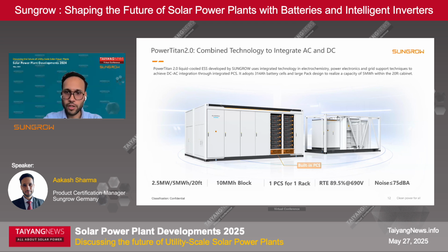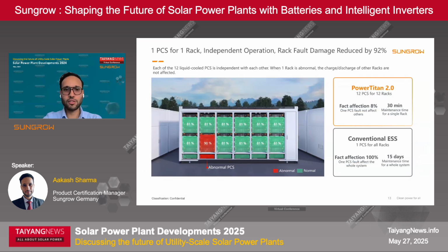Moving on to one of the innovations: it has an integrated PCS. As you can see, we have 12 racks with one PCS each at the bottom, so 12 PCS in total. If one rack, consisting of four battery modules, is at fault, only one PCS is affected, meaning the charging and discharging of other racks and the functioning of other PCS stays unaffected. However, in a conventional centralized energy storage system with just one PCS for all racks, if that PCS is at fault, it can affect the whole system.